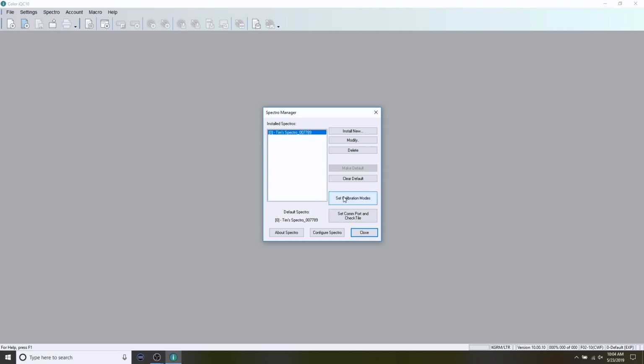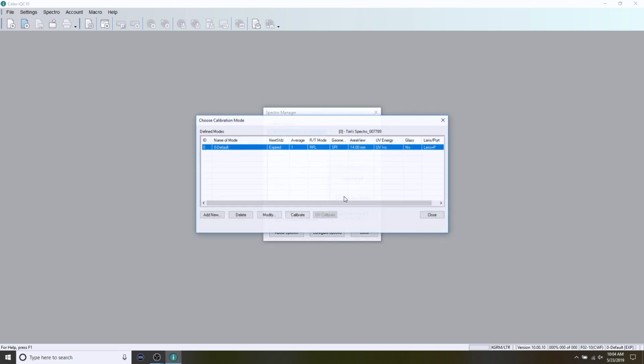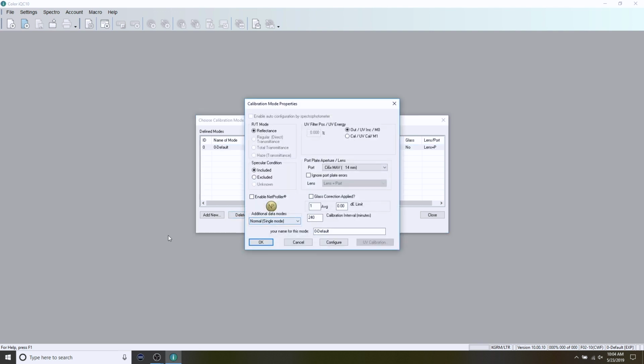And I can choose now to set calibration modes. The default calibration mode is simply using the instrument in its default state. Let's click on Modify to see all the options here. Again, depending on what type of instrument you have, you'll have different options. For example, you'll see there's transmittance, several transmittance and haze measurements. Those are grayed out because I can't do those with a handheld instrument. If I had a benchtop instrument, I'd have those options.